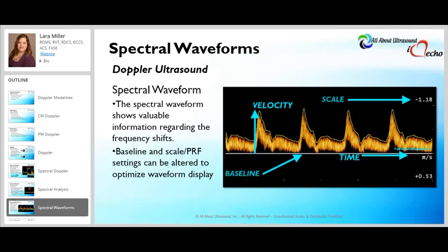The spectral waveform display may or may not be available depending on the system being used. Some small handheld Doppler systems do not display spectral data at all and present Doppler data in an audio format only. However, the spectral waveform display gives very valuable information regarding frequency shifts and is helpful in diagnostic ultrasound. With it, we can visualize the baseline, scale and PRF settings, as well as time and velocity information.